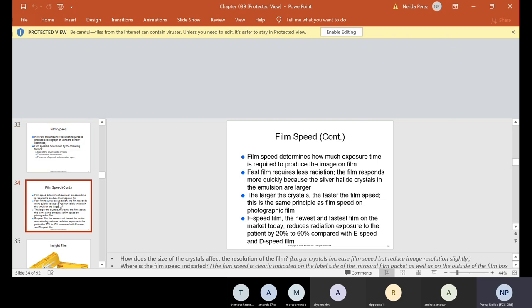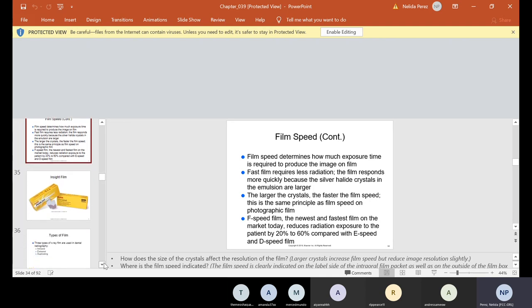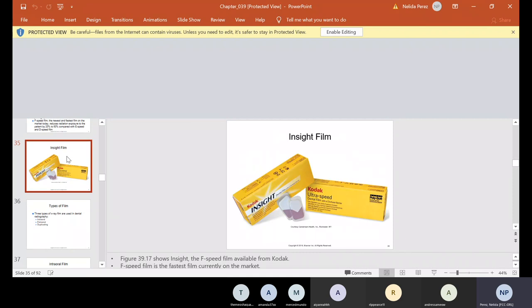Film speed refers to the amount of radiation required to produce a radiograph of standard density — density meaning darkness. Film speed is determined by the size of the silver halide crystals, thickness of the emulsion, and presence of special radiosensitive dyes. Fast film requires less radiation because the silver halide crystals in the emulsion are larger — the larger the crystal, the faster the film speed. F-speed film, the newest and fastest on the market, reduces radiation exposure to the patient by 20% to 60% compared with E-speed and D-speed film.